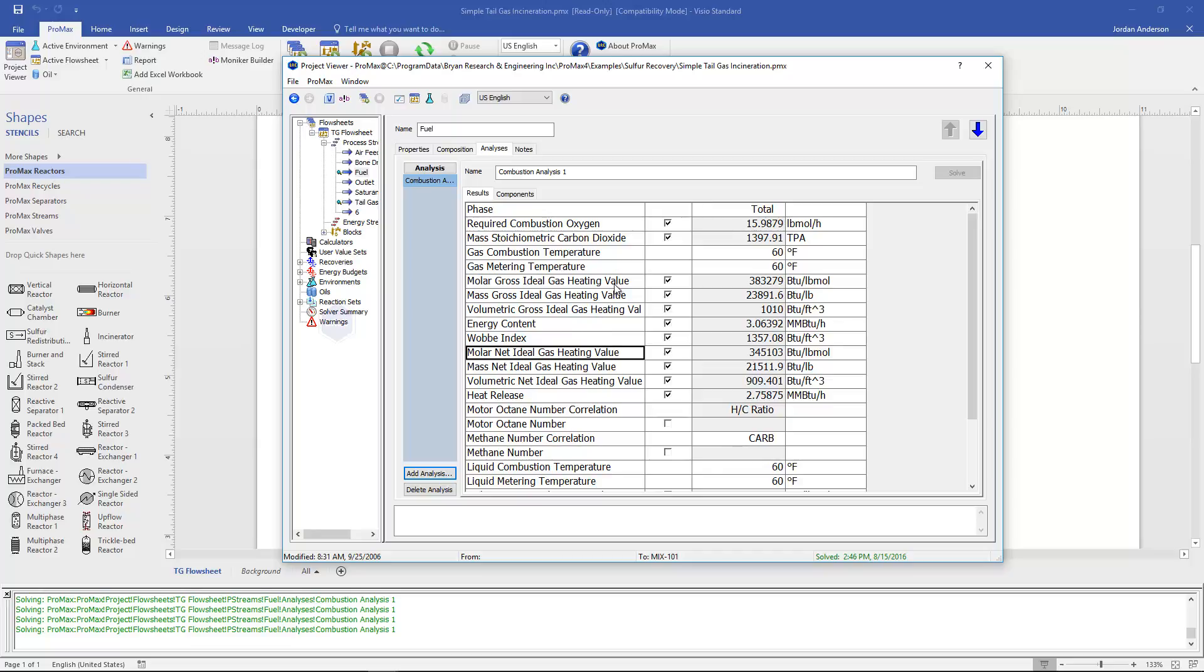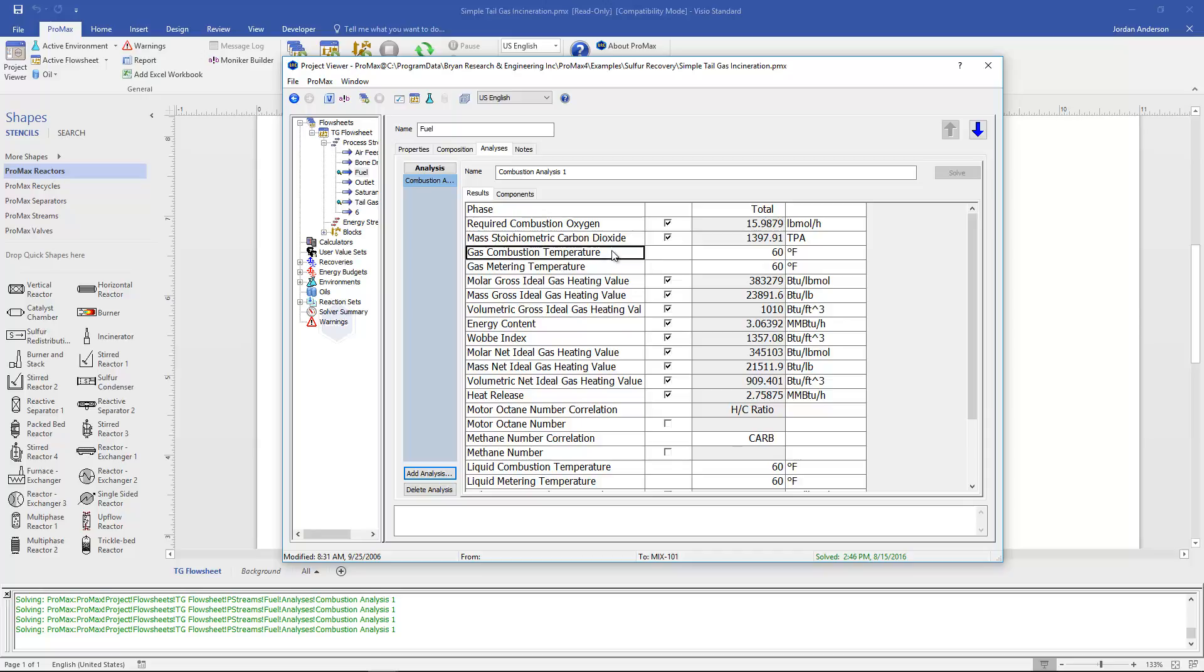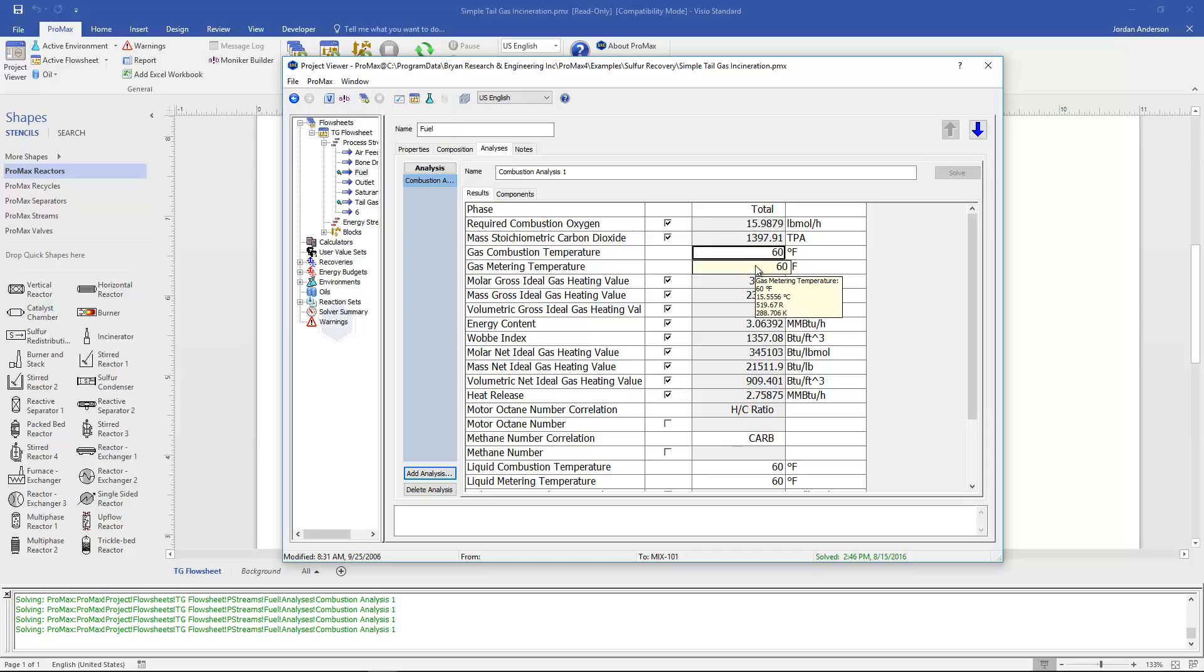It can calculate these on a molar basis, mass basis, and volumetric basis. It's going to perform these calculations based off of our gas combustion temperature and gas metering temperature. By default these values are set at 60 which is the ideal gas reference temperature. But you do have the ability to override these numbers if you would prefer.